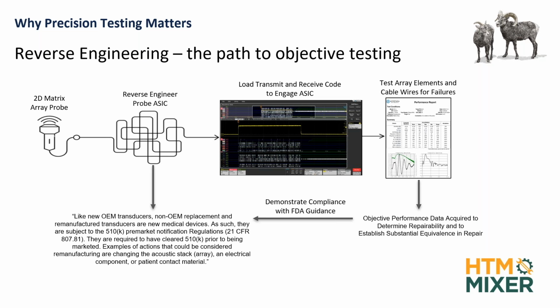What are they doing? So people ask me, well, Wayne, do the OEMs give you all their specifications and stuff on their probes and what materials they use? Not likely. They're not required to do that. That's sometimes proprietary, sometimes patented. So we, and I know other third-party companies have too, have invested in reverse engineering. So for example, I took one, this is a 2D matrix array probe, an X5-1C. It's a phased array probe made by Philips.